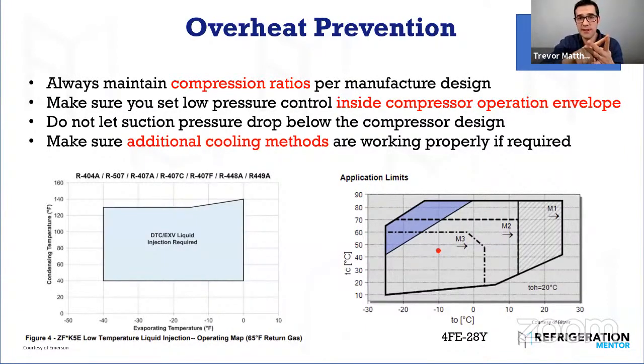And so as it goes to the condenser, it rejects heat and condenses that vapor refrigerant into a liquid. And then that liquid goes to a metering device. The metering device could be a TX valve, electronic TX valve, or capillary tube, which reduces the pressure. The way refrigerant works, you increase pressure, you increase temperature. You decrease pressure, you decrease temperature. So as that TX valve or metering device reduces the pressure, flashing into the evaporator, that evaporator is absorbing the heat from product, from people. And then from there down the suction line, you should have vapor gas going back to the compressor. Hopefully that answered it.